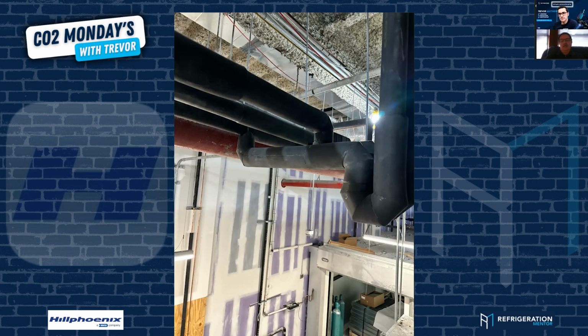Well, I'm glad you mentioned the case piping, especially with CO2. CO2 goes from a huge mass flow to a very low mass flow in a quick time, because once it reaches temperature, it's just going to choke off. The control valve is just going to start cycling 5, 10, 15%. When we do that, we're losing our mass flow. Highly recommend your normal traps, your inverted trap at the top and your regular trap at the bottom. I would use a mid-rise trap on anything over 18 feet. Oh, good. Yeah. Anything over 18 feet. Yep. And then all your piping going back to your risers needs to be pitched that way for your suctions. Yeah. Or 3 or 4 meters. This is stuff we've been doing for 40 or 50 years in the industry.